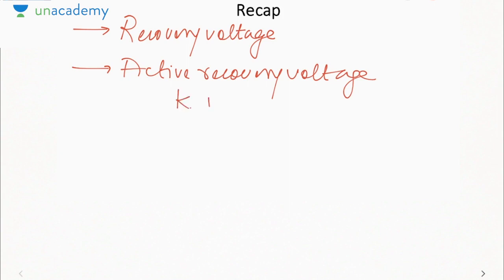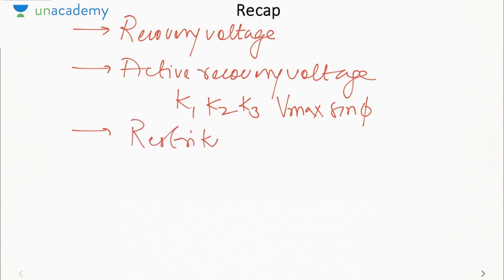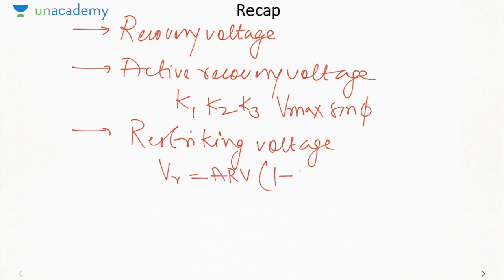This was equal to K1, K2, K3, Vmax sin phi. And the last voltage we saw was restriking voltage, which was the high frequency voltage that appears across circuit breaker contacts at the instant of arc interruption. So it was equal to ARV (1 minus cos t) by under root LC.